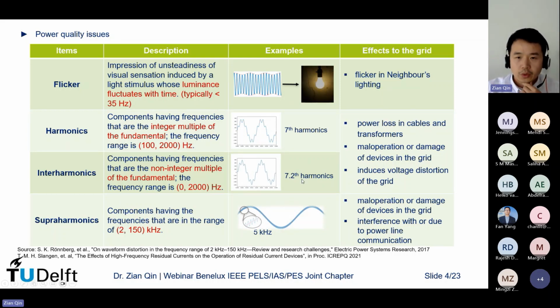If you do a measurement of the interharmonics, you will see something like this: on top of the fundamental, something that looks unstable, resonating all the time. It's not because it's really unstable, it's only because that component has a non-integer multiple of the fundamental frequency. Some people call it harmonic instability, here I call it interharmonics. They are all the same thing.